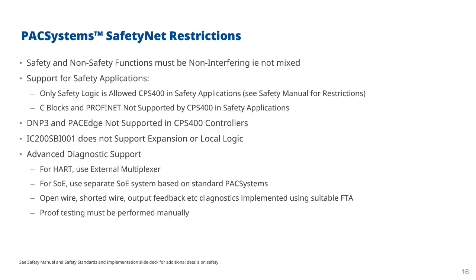Now, because it's a safety controller, PACSystems SafetyNet does have some restrictions. The first is one I've already mentioned. Safety and non-safety functions must be non-interfering, i.e. you don't mix them. So you don't put safety functions in the non-safety controller, because then they will be outside the scope of the safety system. And equally, you don't want your non-safety functions to interfere with the safety function, so you don't put non-safety inside the safety controller. And that's a recognized methodology for doing it. Yes, it puts up the cost of the hardware because you need a safety system as well as a non-safety system. But generally the users of these sorts of systems will accept that and they will be happy with the costs. And of course, you're mitigating the safety issues, which we referred to right back at the beginning of the slides.